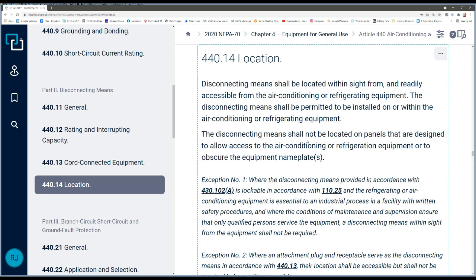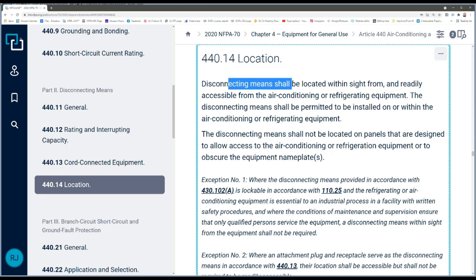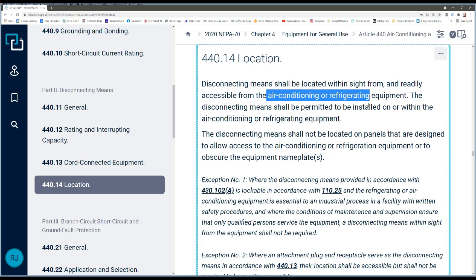The unit on the inside is just an air handler — it's an appliance, so it follows Article 422. Where this gets tricky is the disconnecting means requirements. For the outdoor unit you go to Article 440, and for the indoor unit you go to Article 422. Looking at 440.14: the disconnecting means must be located within sight from and readily accessible from the air conditioning or refrigeration equipment. It can be installed on or in the equipment as long as it's not on panels that obscure the nameplate.